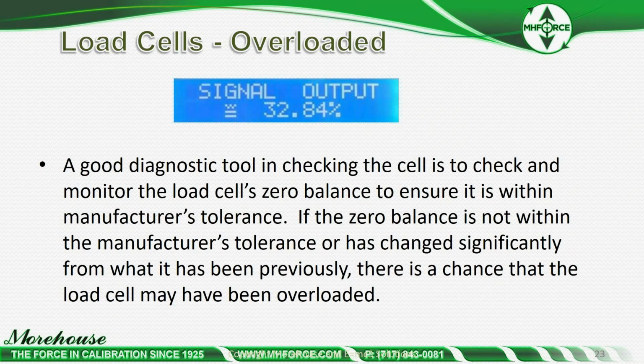So today, you check the zero balance is at 1%. 2 years from now, you check it and it's at 8%. Chances are it's been overloaded. It could be a day, it could be 2 days. It's a good tool. If you're checking this, you have a technician that went out and said, I don't know if I overloaded the load cell or not. If you have the baseline at like 0.1% and now it's at 8%, the tech just overloaded the load cell.